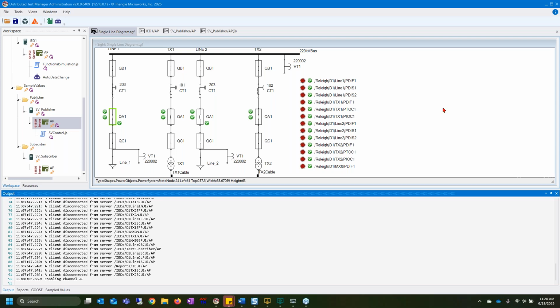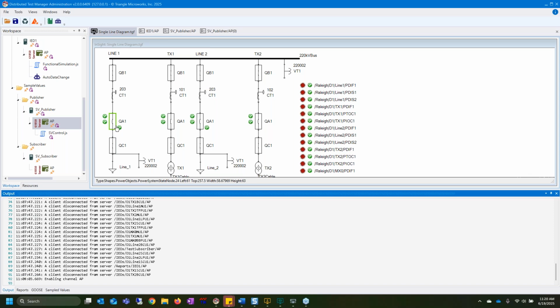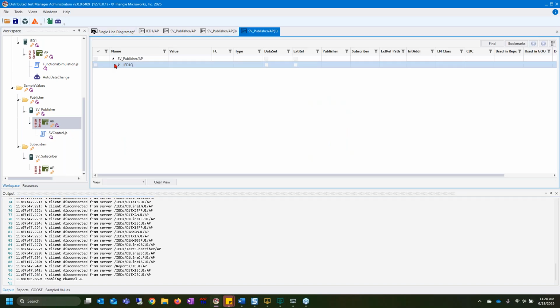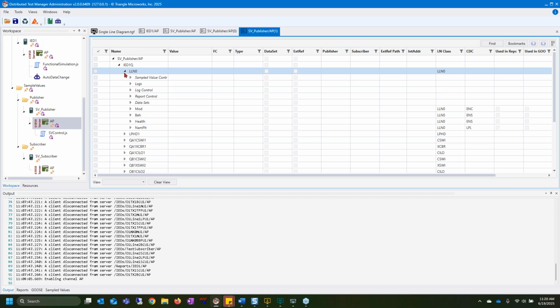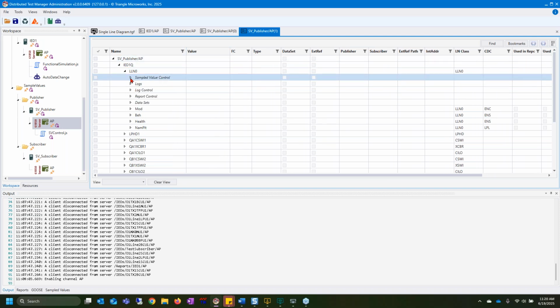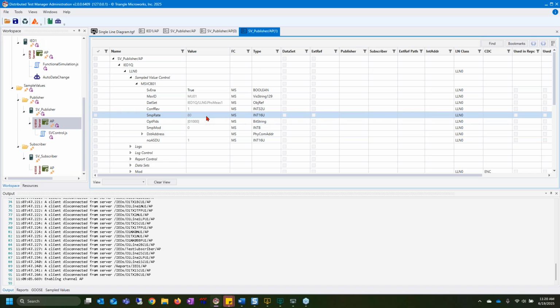Yes, thank you. So just like GOOSE, sampled values is a publisher and subscriber relationship. And the publisher is the one that is monitoring the electrical equipment. So in this case, instead of looking at the previous GOOSE, we're looking at just the state of the breaker. We'll actually be looking at the CT here and looking at the amplitude of the current coming through. Typically, the publisher will be grabbing samples off the line roughly 80 times per cycle. And we can see that configured if we go into the publisher here and do a show model. You can go into that LLN0 where the control blocks are defined. And here is our sampled values control block. And sure enough, we can see sample rate is here at 80.